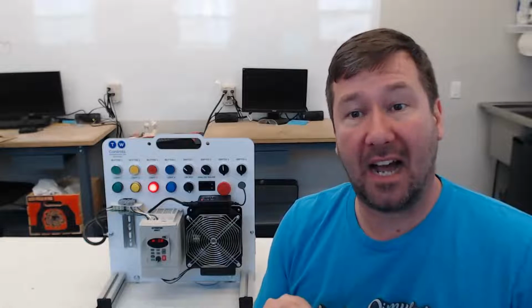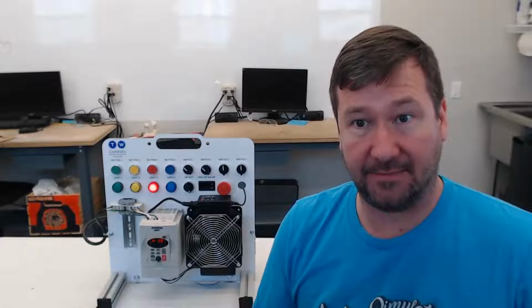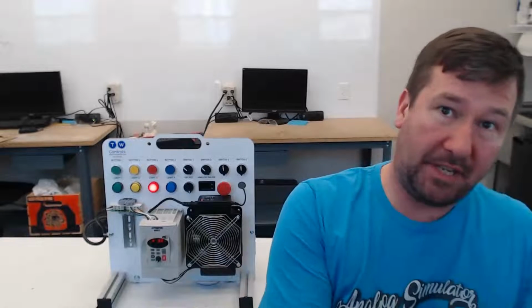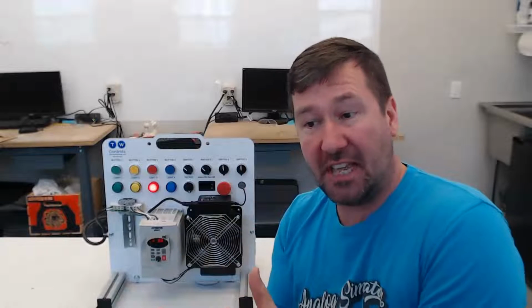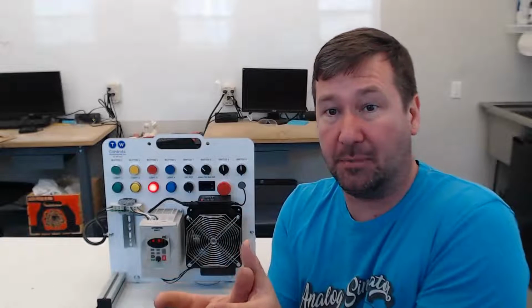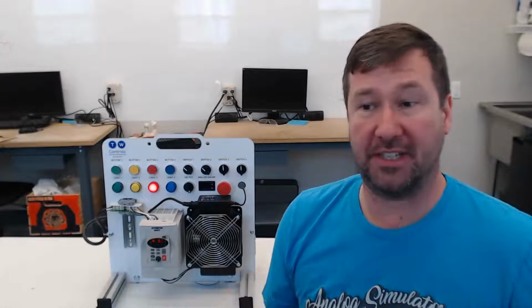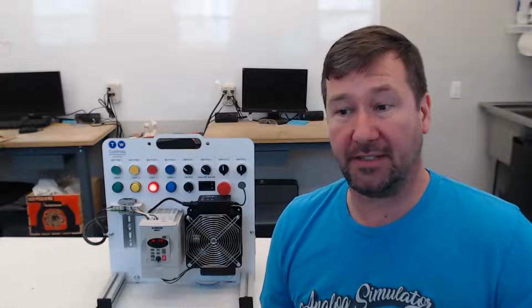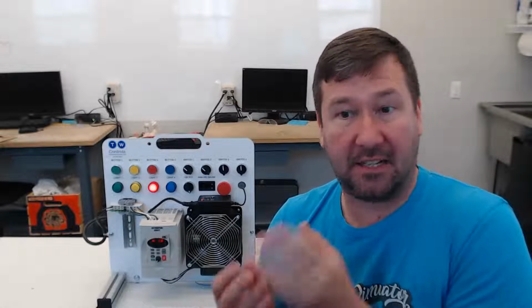So what does the XIC instruction do? This one's big time for instructors. The absolute only real incorrect answer is that it is a normally open contact. Hear that, guys? Scratch that one. I can go with almost anything else you say. But when we try to take PLC ladder symbols and associate them with an electrical symbol, we lose a lot. And that's what causes a large portion of the confusion that you see out there. So the real simple answer is an XIC tells you to go look for a 1.